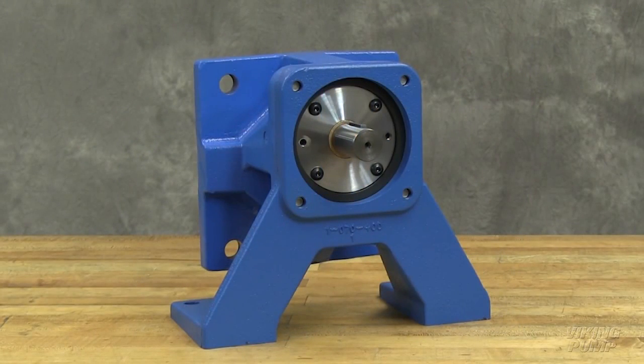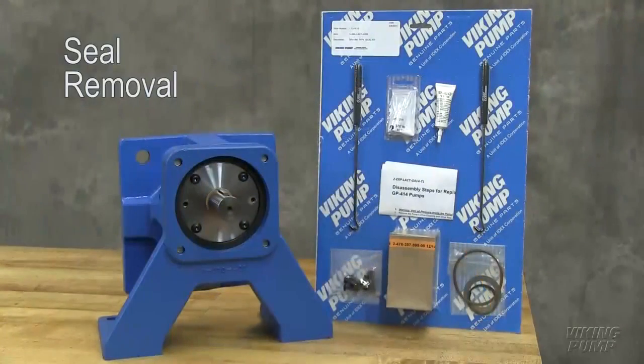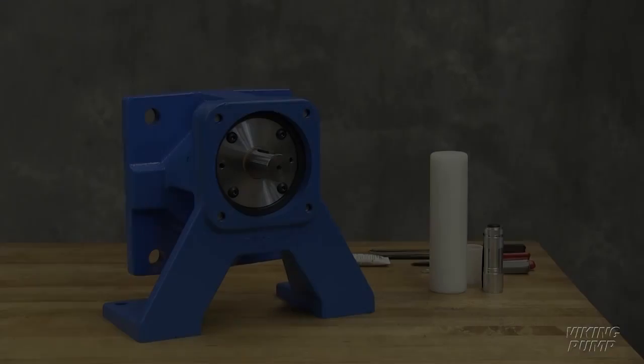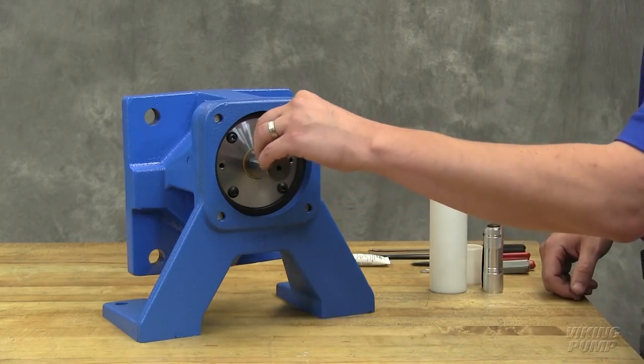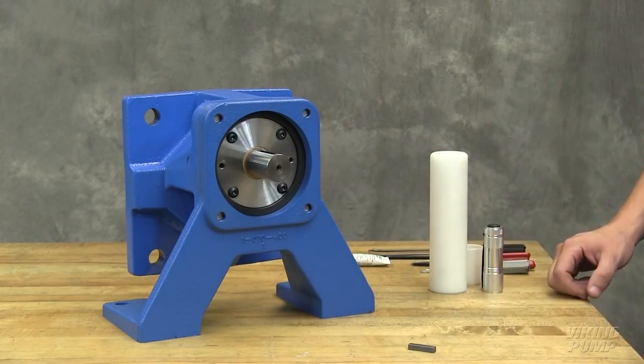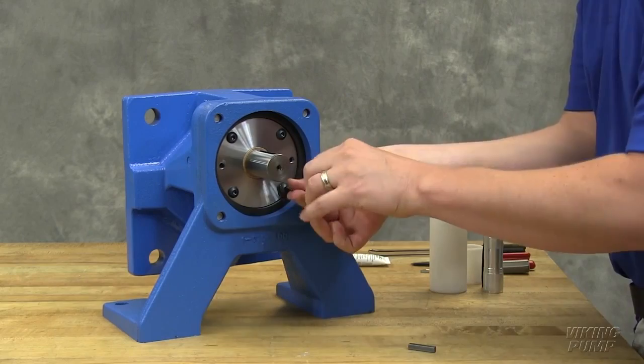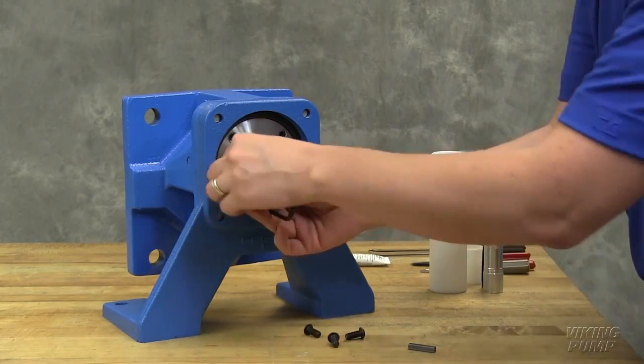Vent all the pressure inside the pump prior to removal of the seal. Keep the pump and work area as clean as possible. Drain the pump of any residual liquid. Turning the shaft will help expel any liquid trapped in the gear teeth. Remove the pump's drive coupling and drive key. Loosen and remove the seal holder cap screws.